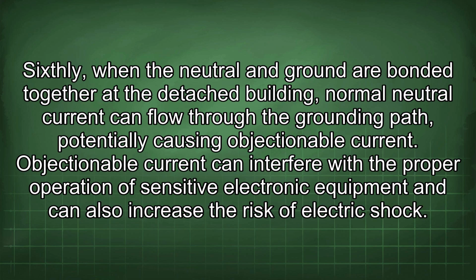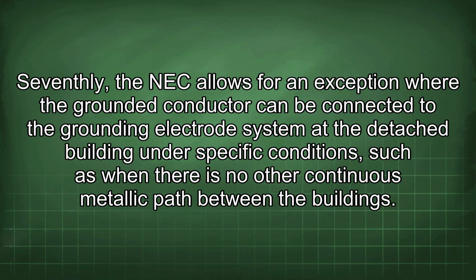Sixthly, when the neutral and ground are bonded together at the detached building, normal neutral current can flow through the grounding path, potentially causing objectionable current. Objectionable current can interfere with the proper operation of sensitive electronic equipment and can also increase the risk of electric shock.